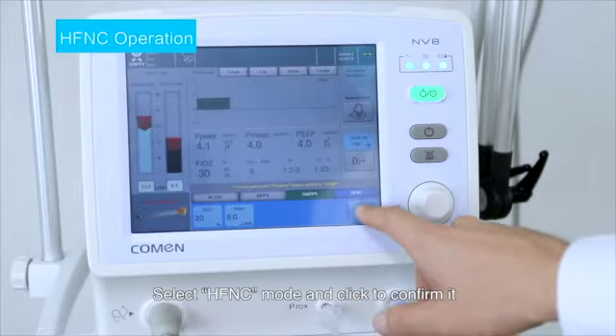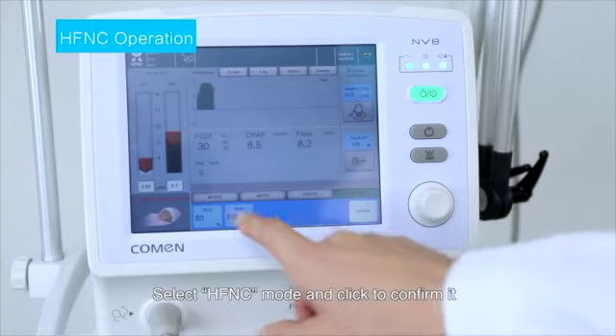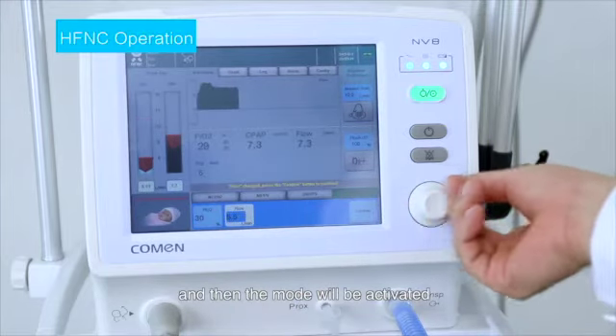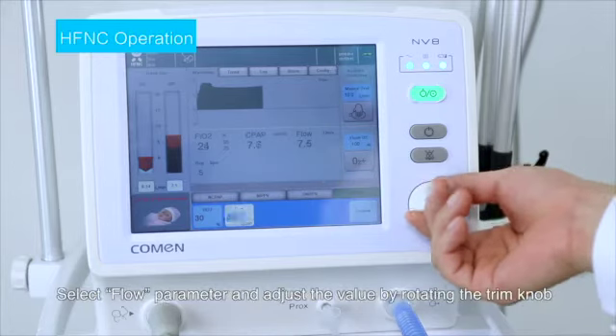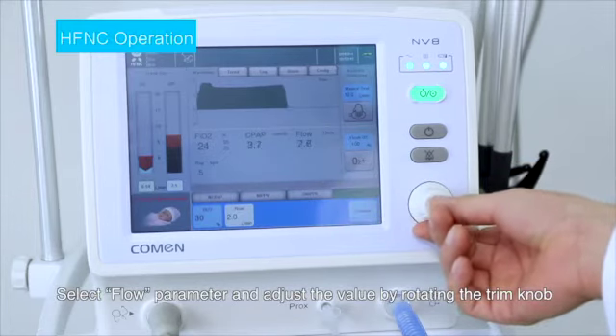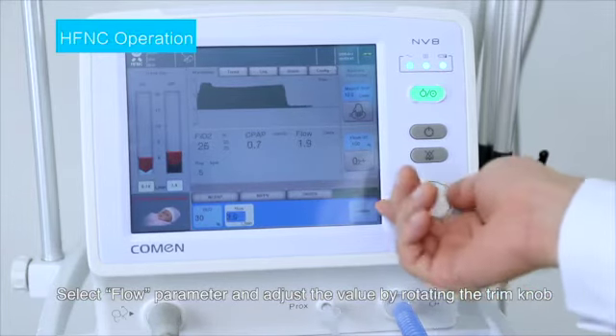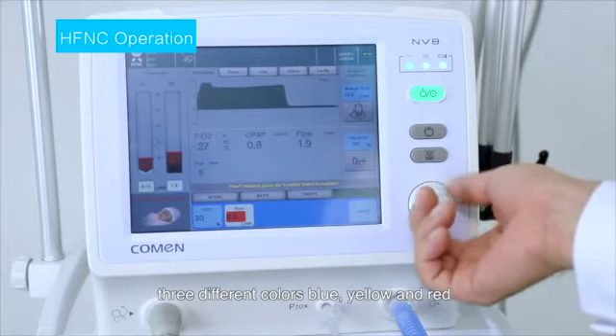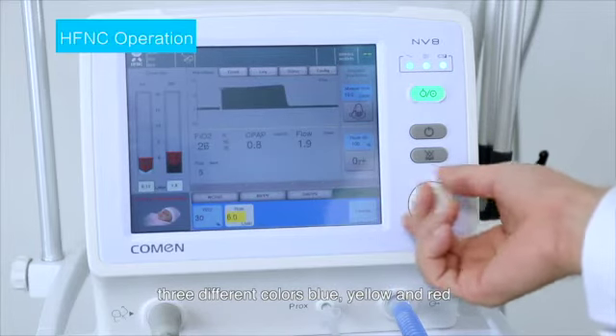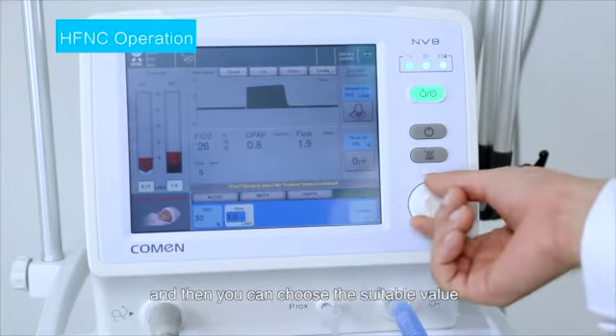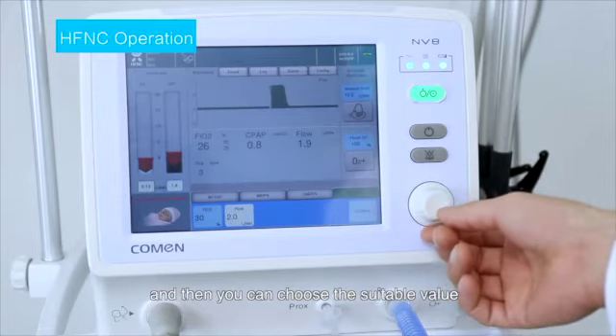HFNC mode selection and operation. Select HFNC mode and click to confirm it, and then the mode will be activated. Select flow parameter and adjust the value by rotating the trim knob. 3 different colors blue, yellow, and red indicate different flow value, and then you can choose the suitable value.